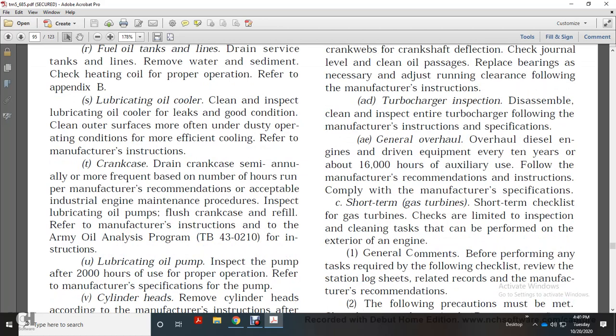Crankcase: drain the crankcase semi-annually, or more frequently depending on the number of hours run per the manufacturer's recommendation, or acceptable industrial engine maintenance. Proceed to inspect the lubricating oil pump, flush the crankcase, and refill per the manufacturer's instructions. See the Army Oil Analysis Program Technical Bulletin 430210 for instruction.